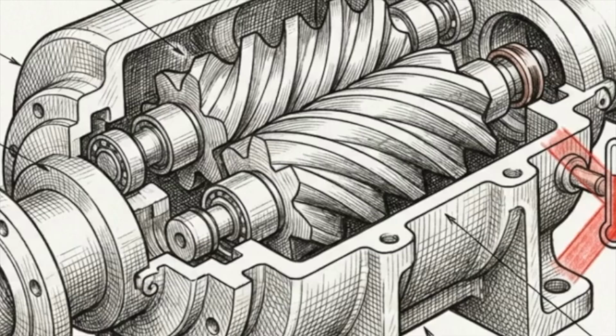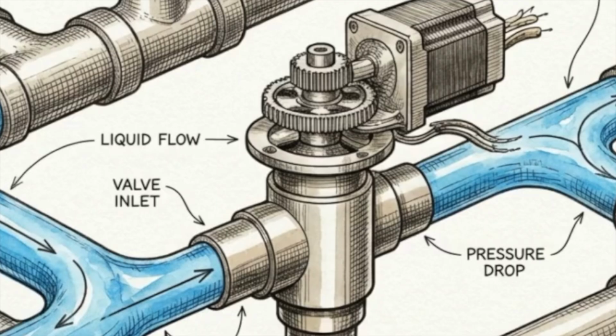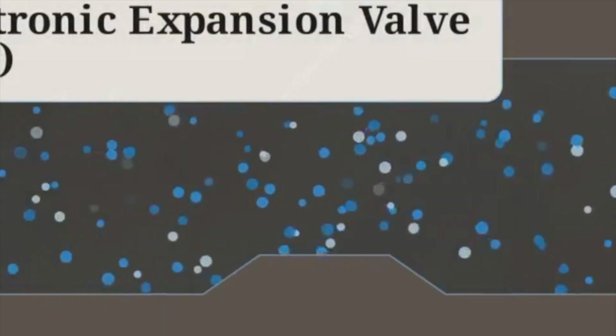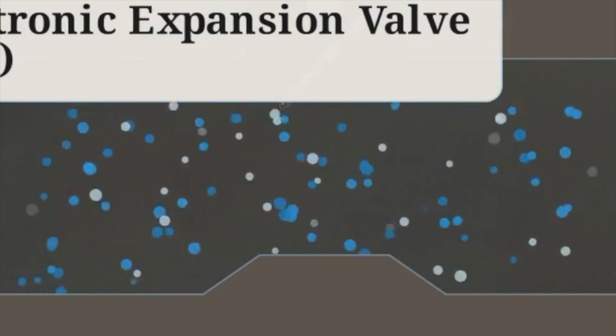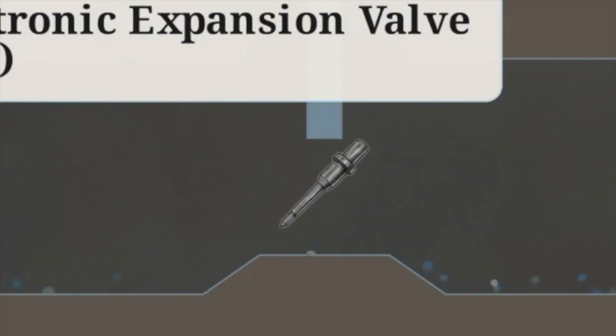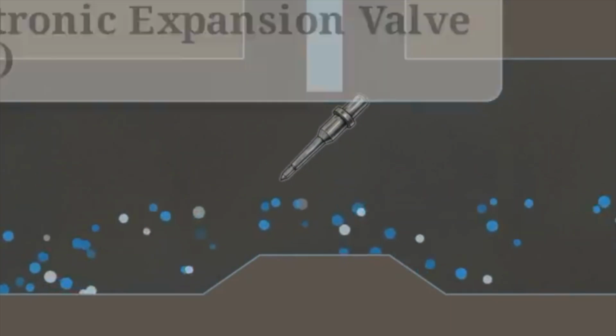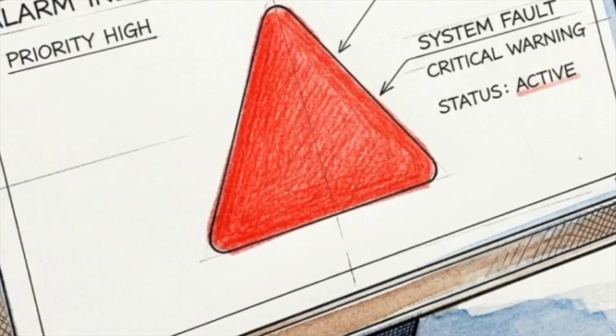Stopping liquid slugging requires a pivot in engineering logic. Operators must stop monitoring the trailing temperature of the casing and start tracking the mechanism actually controlling the fluid. That control point is the electronic expansion valve, or EEV. It dictates the exact volume of refrigerant entering the evaporator. Currently, facilities inspect these systems through periodic manual checks with a clipboard, or they simply wait for a low-pressure safety trip to automatically generate a maintenance ticket.